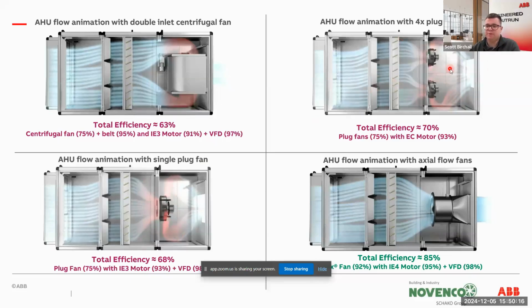as you can see in this top right one, where it's multiple fans all together to keep these things operating. A lot of times they'll claim it as redundancy, where if one fails, another will pick up, and all that kind of stuff. But if you do that, you have to have walls installed and isolation dampers. And we've seen a lot of these in real effect where they're not really used as a redundant system. They're just operated as they are, and if one fails, it needs to be swapped out. So that's something to consider as well.